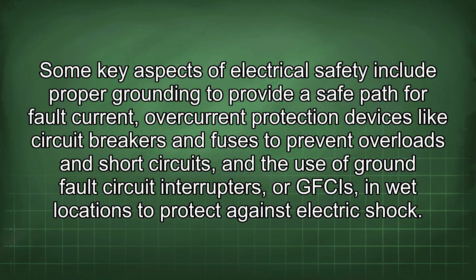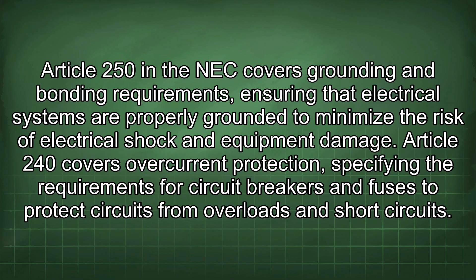Article 250 in the NEC covers grounding and bonding requirements, ensuring that electrical systems are properly grounded to minimize the risk of electrical shock and equipment damage. Article 240 covers overcurrent protection, specifying the requirements for circuit breakers and fuses to protect circuits from overloads and short circuits. Article 210.8 covers ground fault circuit interrupter protection, requiring GFCIs in bathrooms, kitchens, and other wet locations to protect people from electrical shock. Understanding and adhering to these NEC articles is essential for electrical safety.